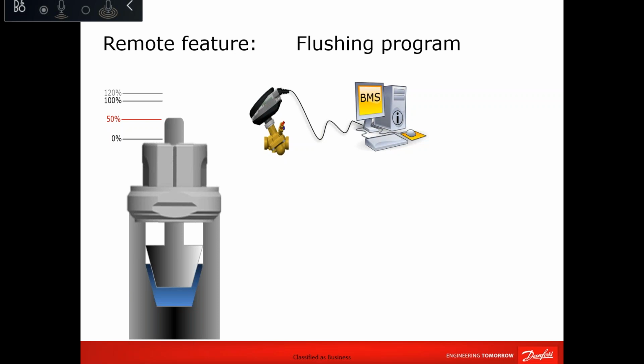And if you have your full project set at different settings, you don't want to go everywhere and open every valve. So once you hit the flushing program, it will disregard your setting for a predefined time. And this time, which in your example is 60 minutes, is controllable. You can set that time. You can put it 3 days, 1 week, 1 hour. So this is the flushing. Once the flushing is done and the time has elapsed, then it will return back to the original setting.